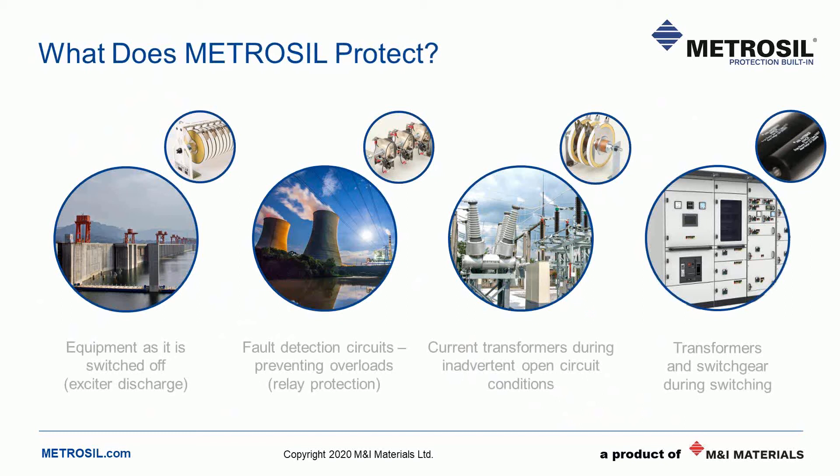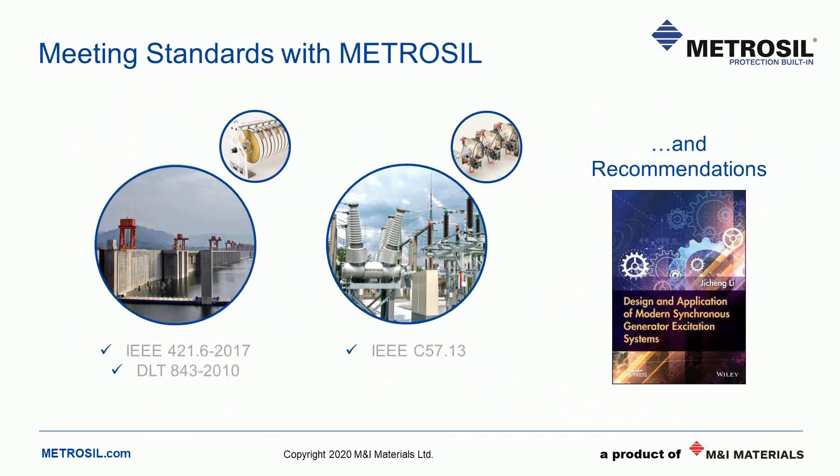There are many other applications where Metrosil is used to stop overvoltage and limit current surges. Examples of relevant IEEE regulations include 421.6-2017, the recommended practice for the protection of synchronous machines, which recommends silicon carbide varistors for fast, high-energy discharge for critical protection of generator systems. DLT 843-2010 is a Chinese power system standard maintaining overvoltage protection. IEEE C57.13 is an instrument transformer standard which covers CT protection. Metrosil ensures these standards and practices are met, and Metrosil products are recommended by large electrical OEMs in technical publications.